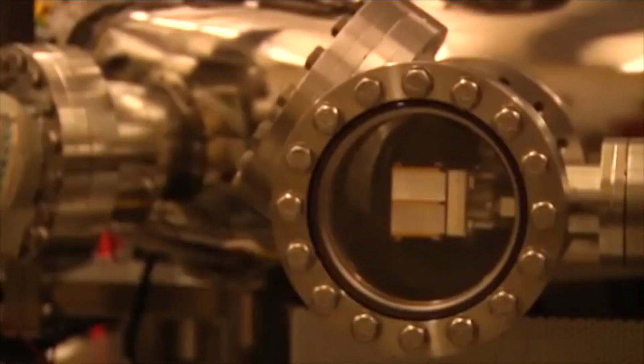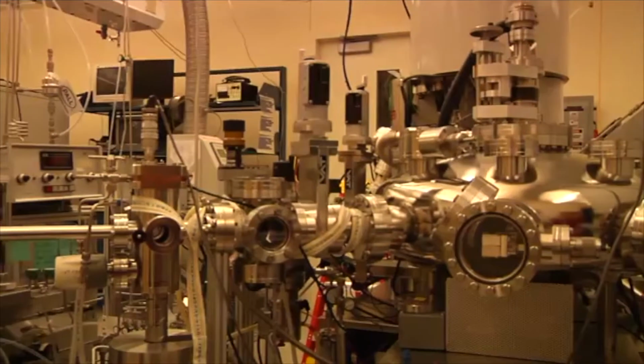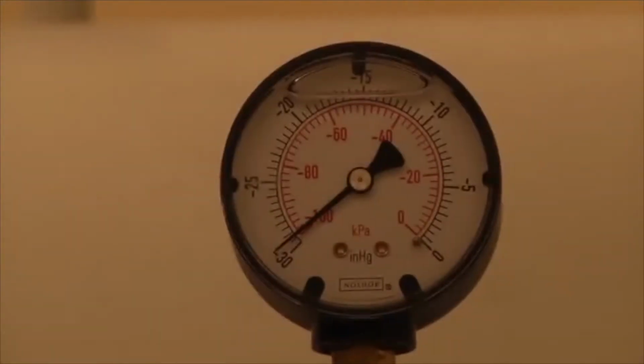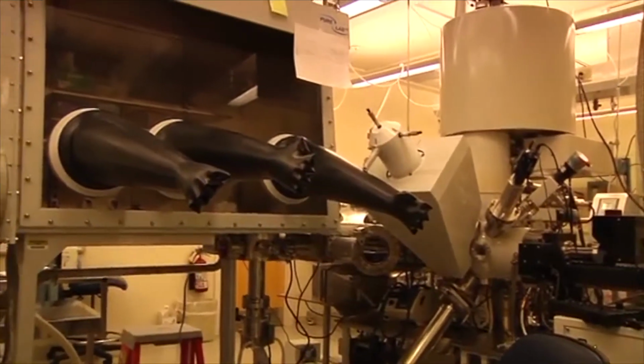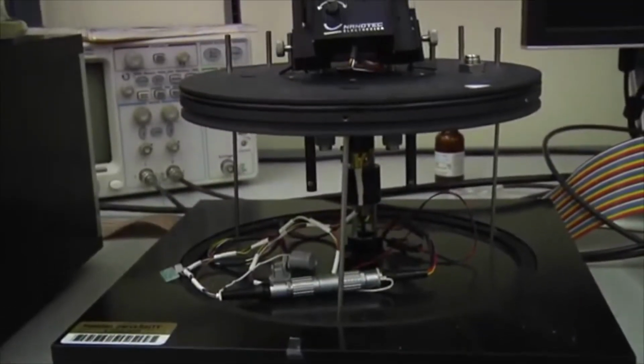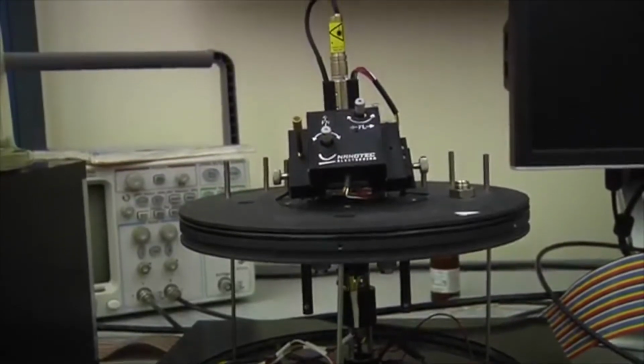Probably the most impressive of the laboratories outside the clean room is the Hall Nanometrology Laboratory. There we designed the room to control temperature, electromagnetic interference, and vibration. These three factors are very important. Vibration matters because movement will cause problems when working on precise measurements at the nanoscale. Temperature matters because things change size as they change temperature. Electromagnetic interference matters because we move things around using electric and magnetic fields, what we call nanotweezers, where we're actually moving individual atoms around, and stray fields would interfere with that.